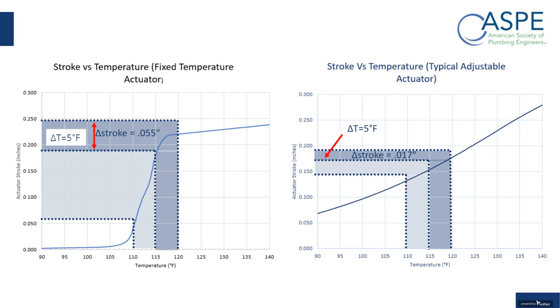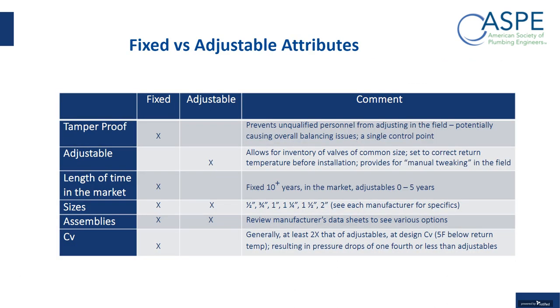So from 110 to 120, this valve will stroke from a little bit above 0.05 to 0.25. So a very large stroke, relatively speaking. For that same temperature range for the adjustable, from 110 to 120, that valve is stroking from a little bit less than 0.15 to maybe 0.18. So this is giving you 4 times the stroke that the adjustable gives you for the same temperature change. That results in a CV change that's a lot lower and would result in a lot higher pressure drop. Again, it's not the end of the world. It just means you have to take that more into consideration when you're designing or specifying your pump.